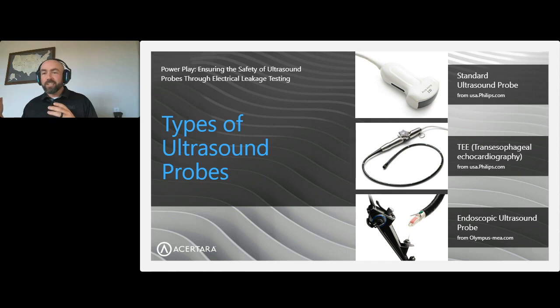And that's when you get fluid ingress into that device, you can have opportunities for cross-contamination. And more than likely, in my experience, I've been doing this 26 years, a lot of ultrasound probe repair through that time, you're going to often destroy your probe. You're going to have problems with your transducer there and cost time and money for the hospital, but also present a danger to the patient.